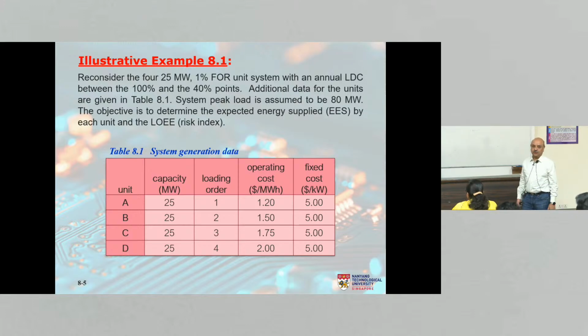So they are fixed. They do not depend upon one generator being out of service or not producing its full capacity. It's constant. Every year you pay the premium, insurance and rental and whatever else. That's why it's called fixed cost. So if I have these two data, I can calculate the total cost of generating that much energy using the operating cost as well as the fixed cost. That's very useful to the system planner when you can calculate the total cost of production of a certain amount of energy. So we'll not use this for now, but I wanted to tell you where these numbers are coming from and how we can use them, okay?